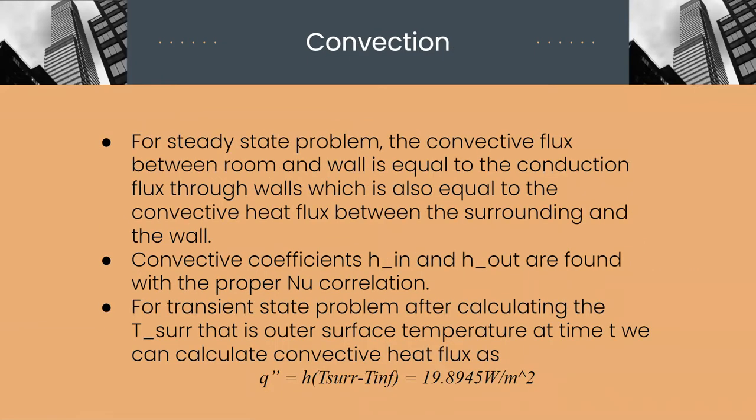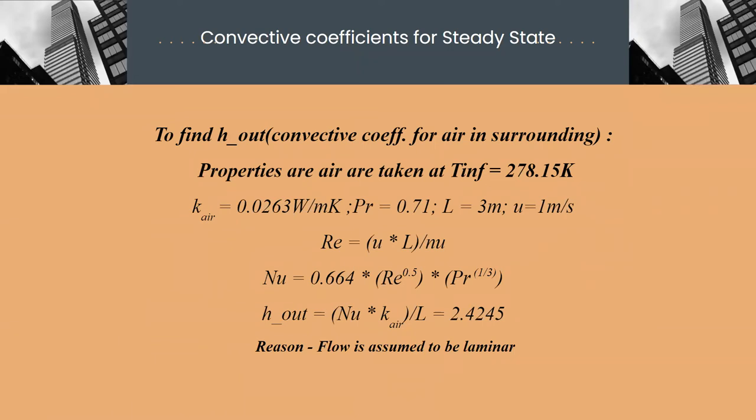Coming to convection, the convective heat flux between room and wall is equal to the conduction flux through walls which is also equal to the convective heat flux between the surrounding and the wall. Convective coefficients h_in and h_out are found with proper Nusselt number correlations. And for transient problem, convective heat flux is calculated at time t by calculating temperature of outer surface. Equation used to calculate heat flux is shown below.